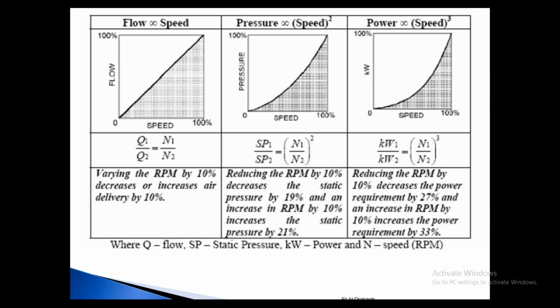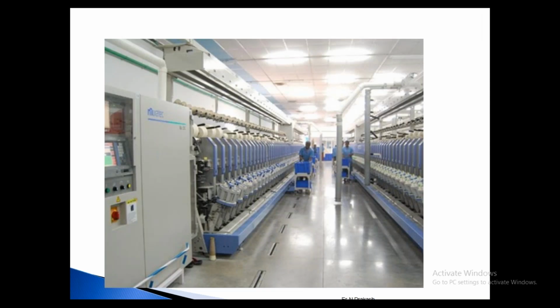Either from the mill side or management side, or from the external consultant or auditor side, we have to collect the information from the customer. Full information we should have: at what level you are going to run the plant, what your required parameters are for the best production and productivity, and your exact requirement. Then based on that, we can recommend what kind of fan, whether we reduce the fan or reduce the speed. All these actions we can take as an energy auditor.